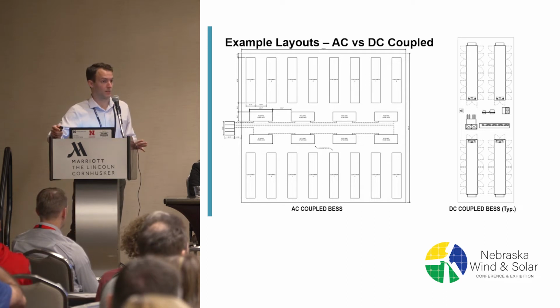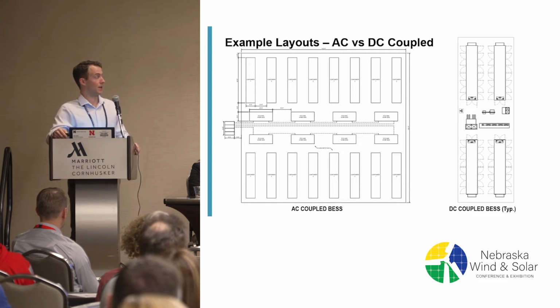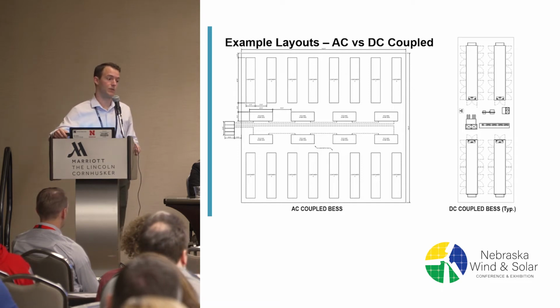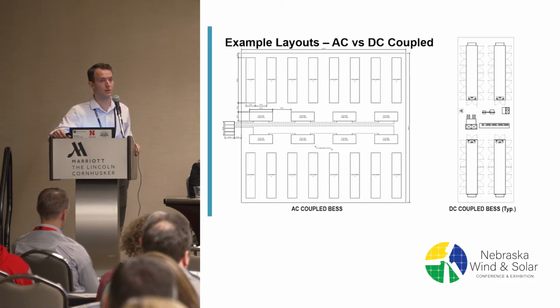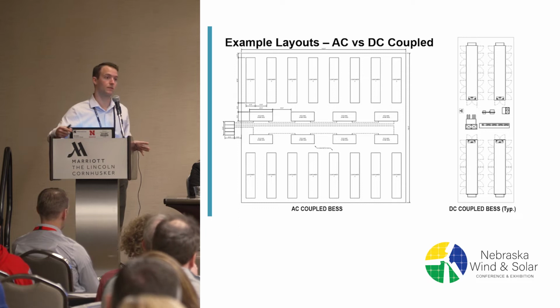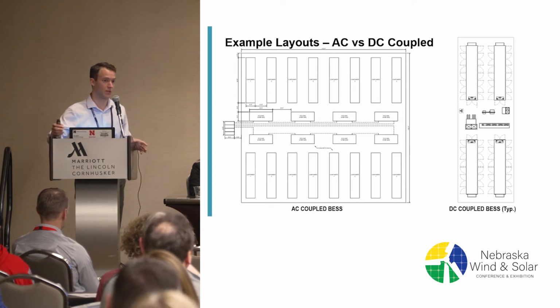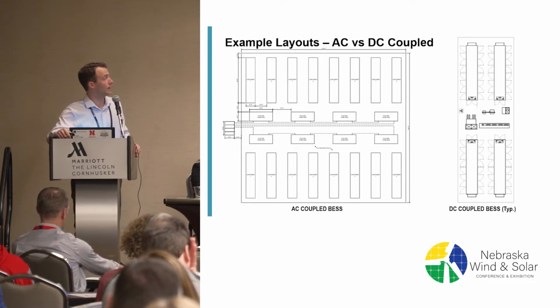There's a lot of flexibility in it, including flexibility in power and energy ratio. Generally, most lithium systems are pre-configured for 1, 2, or 4 hours. But based on how that C rate and power-to-energy ratio is laid out, you'll have different quantities of containers and their associated inverters and transformers. So the ratio of equipment changes from one project to another.